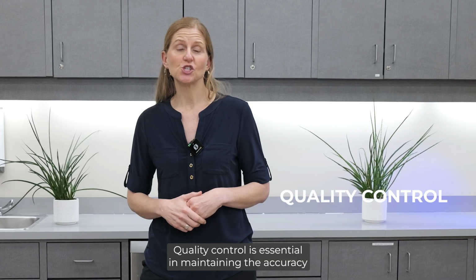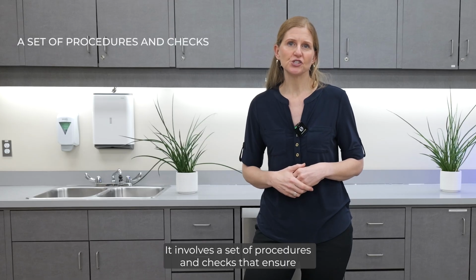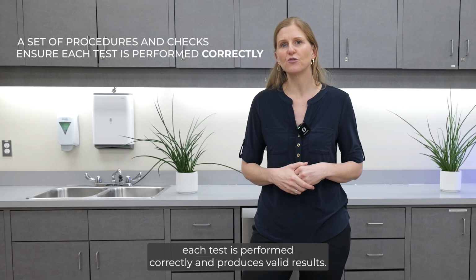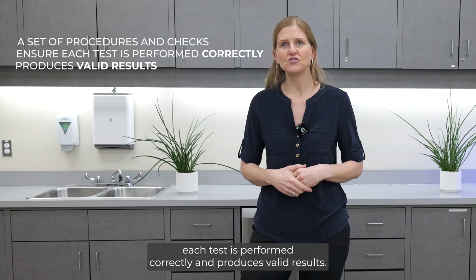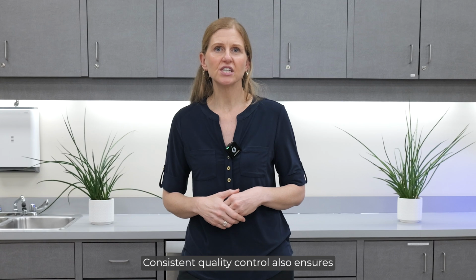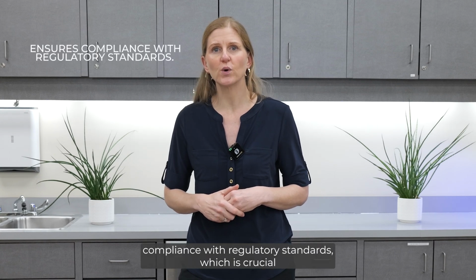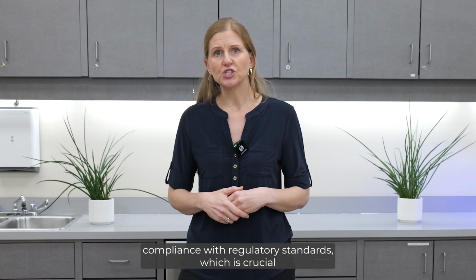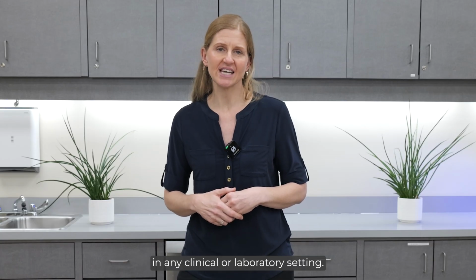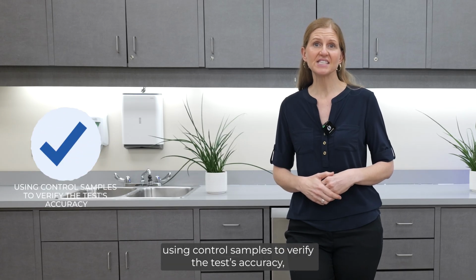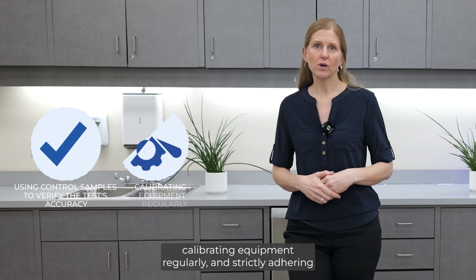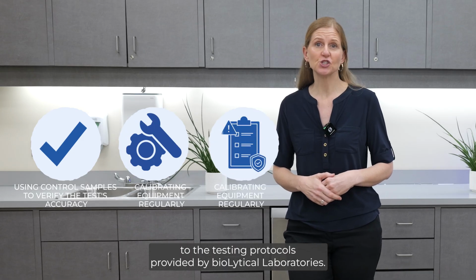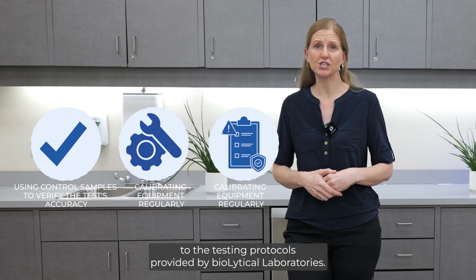Quality control is essential in maintaining the accuracy and reliability of the INSTI Multiplex test. It involves a set of procedures and checks that ensure each test is performed correctly and produces valid results. Consistent quality control also ensures compliance with regulatory standards, which is crucial in any clinical or laboratory setting. Quality control includes using control samples to verify the test's accuracy, calibrating equipment regularly, and strictly adhering to the testing protocols provided by bioLytical laboratories.